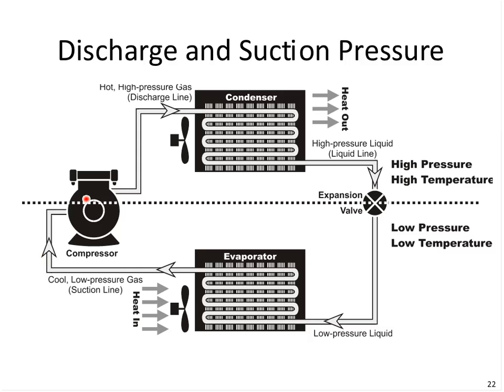So when we talk about suction temperature or pressure reset at this point here, it's just affecting how the compressor is loading. If the compressor is loading with a slide valve, then it's just going to actuate the slide valve at a higher temperature than a lower temperature. If it's variable speed on the compressor, then it would just slow the compressor down. And that's where we get the energy savings.